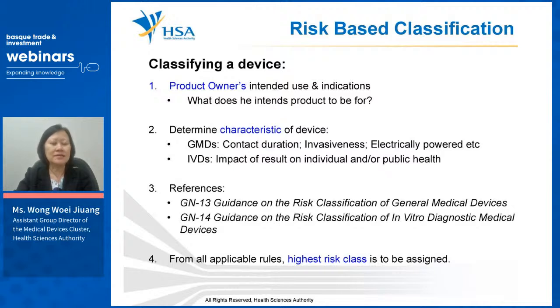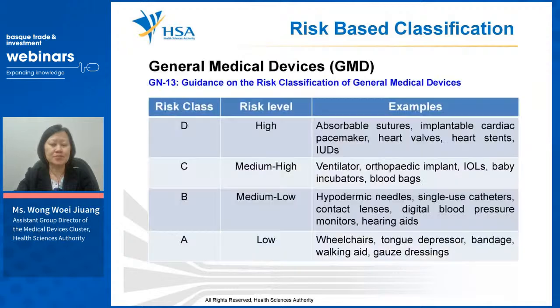So who then decides on the classification of the device? It is based on the product owner's intended use and indication. The product owner refers to the manufacturer: what he intends the product to be for, and what the characteristics of the device are. He has to determine the characteristics, which would determine the contact duration, invasiveness, and whether the impact on public health or the individual is high. We have reference guidance documents on our website that touch on risk classification. So this is the general risk class for general medical devices. Class A is considered low risk, and Class D is high risk. So it's A, B, C, D, four levels of risk classes.